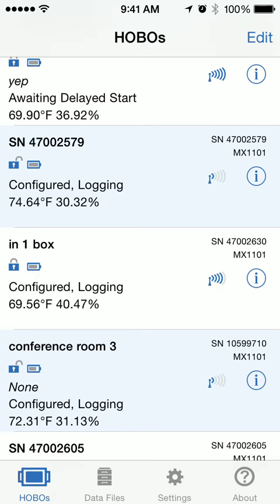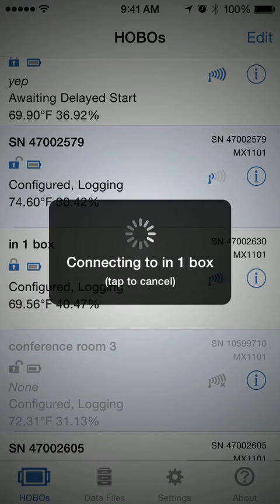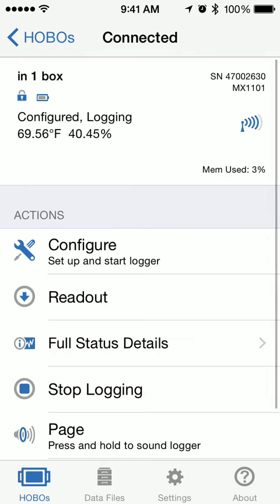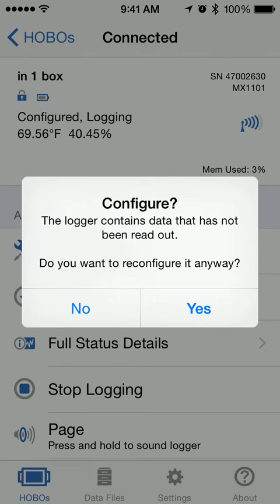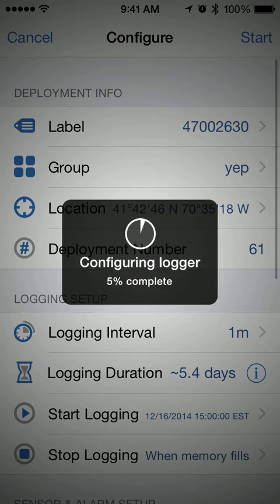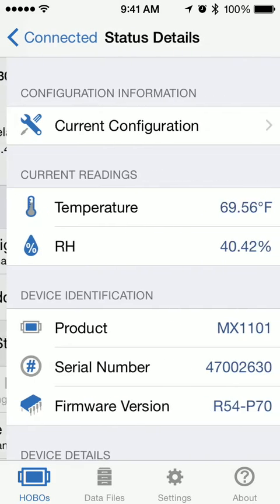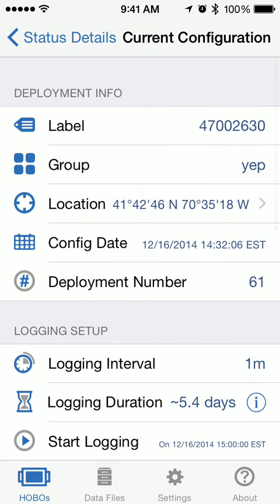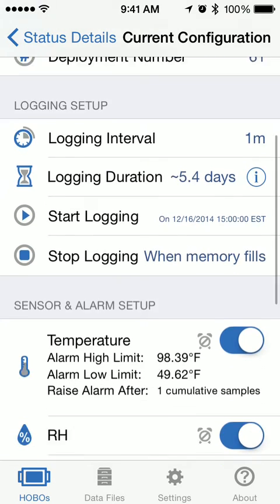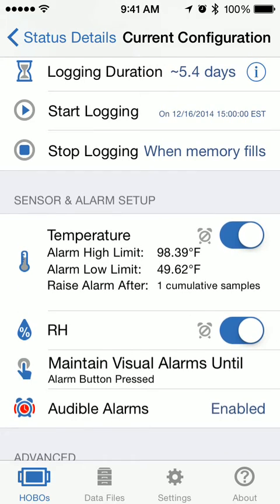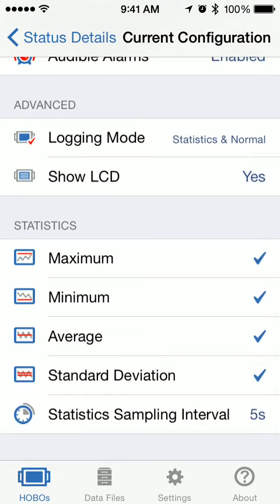As you can see, it says in one box it's currently configured and logging. We'll tap on it, then tap Configure — it asks if we really want to do this, and yes, we do. Automatically, it sends the information out. As you can see, it changed the label to the serial number, put it in the YEP group, and it's waiting for a delayed start. To confirm the rest of the status, tap Full Status Details and then Current Configuration. You can see we're waiting for a delayed start at 1500 hours, with the high and low temperature alarm set, the audible alarm enabled, and all of the statistics.